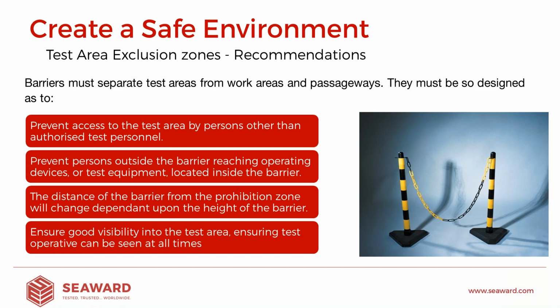Again, if the worst was to happen to the operator, we want to make sure that someone always has an eye on him at all times, so that he's not potentially left to continue receiving an electric shock if the absolute worst was to happen. So we certainly wouldn't advocate creating a totally enclosed room where only the test operator goes in to perform the test. If you do that kind of setup, certainly make sure you have windows where it's possible to see.